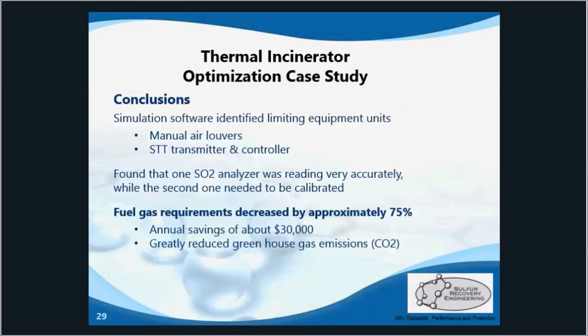The simulation software was able to identify limitations in terms of reducing combustion airflow and the resulting excess oxygen in the stack. We found that the manually adjustable air louvers were greatly limiting the minimum combustion airflow that could be achieved — there was just too much airflow even when they were almost fully closed. The lower reading limits were also determined with the STT transmitter, the stack top temperature transmitter, as well as the minimum acceptable input value for the controller. By reducing the stack top temperature to 325 degrees Celsius, the fuel gas requirements dropped by about 75%, corresponding to an annual savings of about $30,000 a year, and it greatly reduced the CO2 emissions from the stack — huge gains.